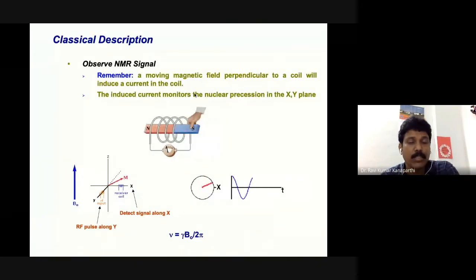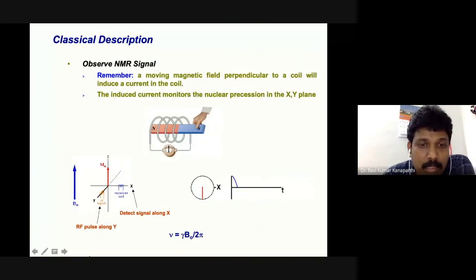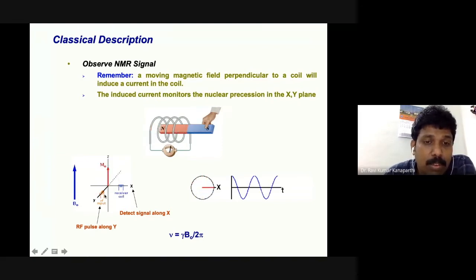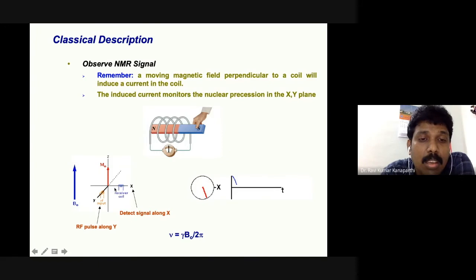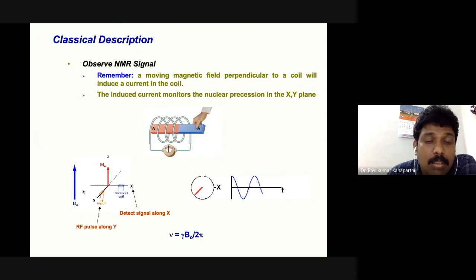And this is what I was referring to. And this is where it is given very nicely. Two different coils you can see here. This is the transmitter coil, written as RF input. And this is the receiving coil. Once you apply the radio frequency pulse, that will tip, as you have seen in the previous animation, and circulate the magnetization in the XY plane. The moment B1 is stopped, the receiver coil starts detecting the signal from the net magnetization vector.